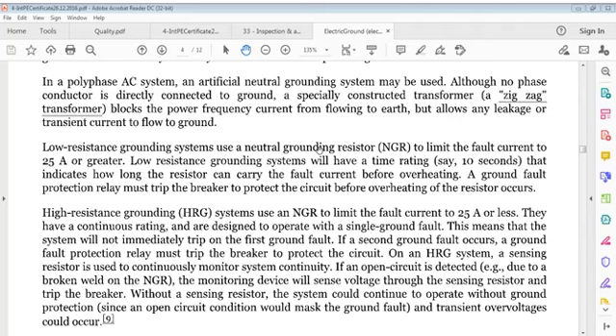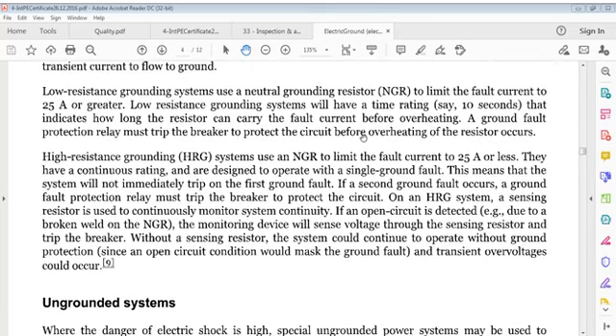Polyphase means three phases or more phases, not single phase. In a polyphase AC system, an artificial neutral grounding system may be used. Although no phase conductor is directly connected to ground, a specially constructed transformer blocks power frequency current from flowing to earth, but allows leakage or transient current to flow to ground. Low resistance grounding systems use a neutral grounding resistor, NGR, to limit fault current to 25 amperes or greater.